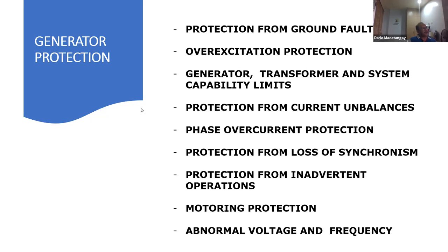We need to maintain the operation of the generator within the limits of the generator, transformer, and system capability. We're talking not about the generator only, but also about limits on the generator, the transformer, and how it affects the power system, the transmission system, as well as the turbine sometimes. We need to protect the generator from current imbalances, negative sequence currents.